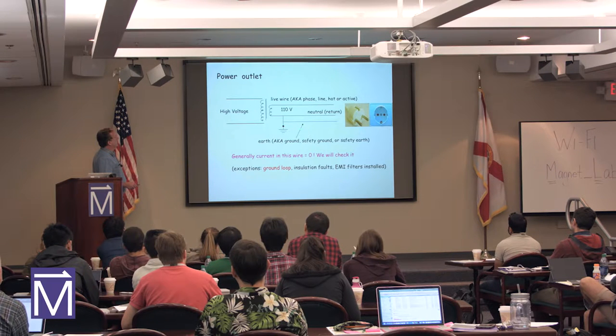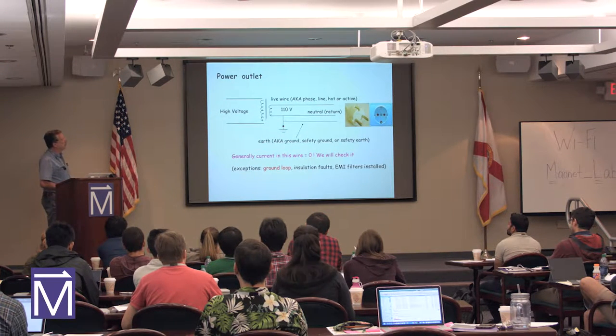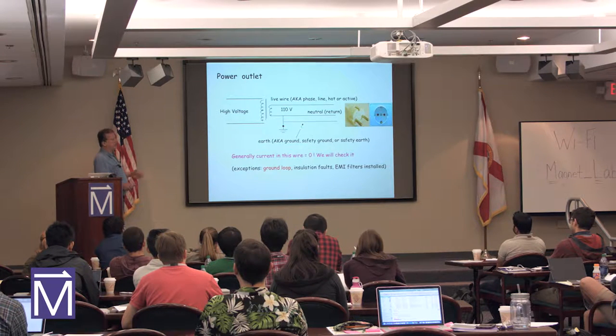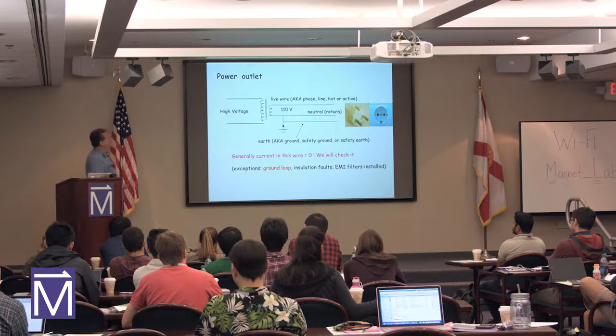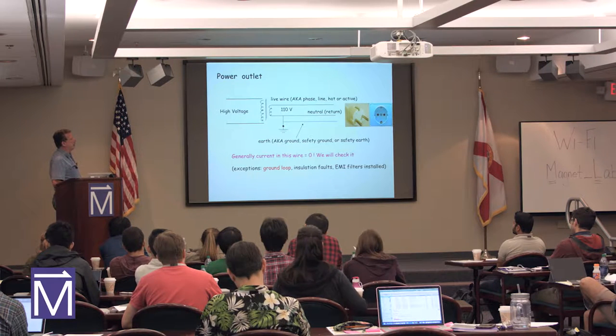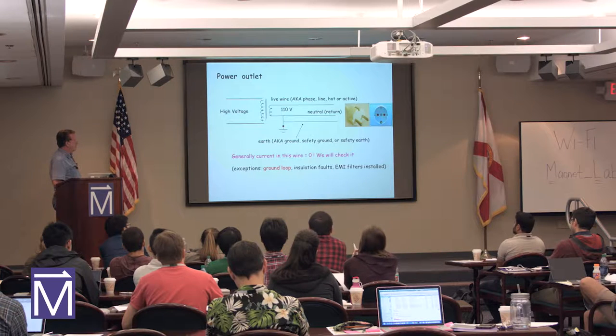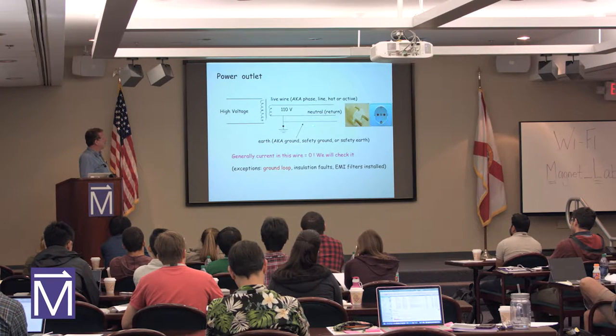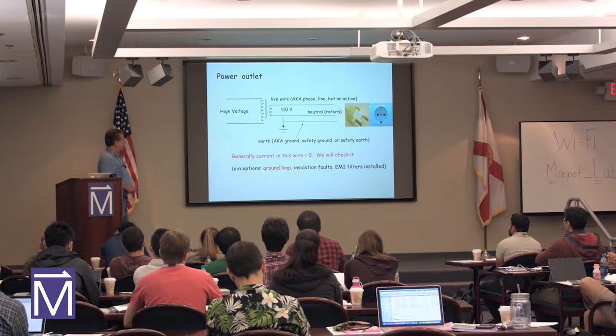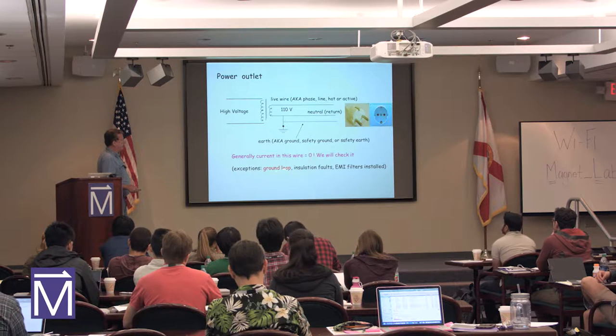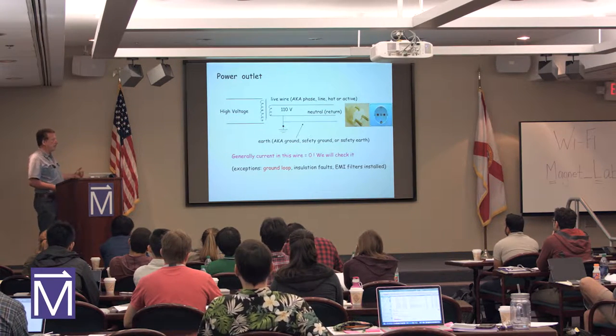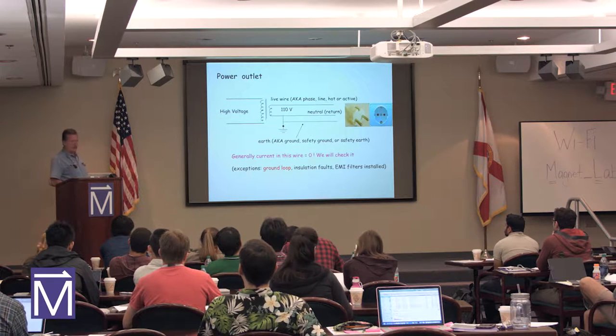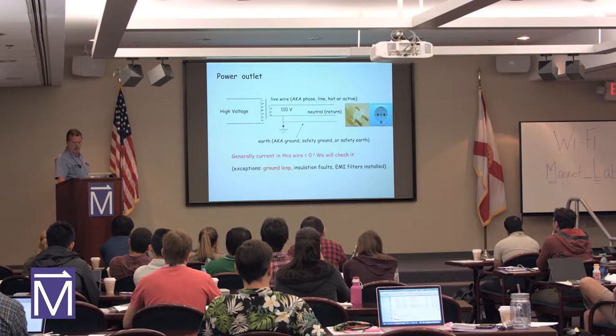Sometimes those cables go individually to each room and even individually to each outlet, not in this lab, to provide a so-called clean lab, clean ground, so that if anybody in the room connects something very noisy to this ground or has a strong leak, you can still use the clean ground. Generally, current in the ground wire should be zero. We will check it during our practicals in cell four later today and tomorrow. Exceptions are when there is a ground loop, insulation faults, or an electromagnetic interference filter installed on the input of your instrument, which puts some high frequency to the ground.